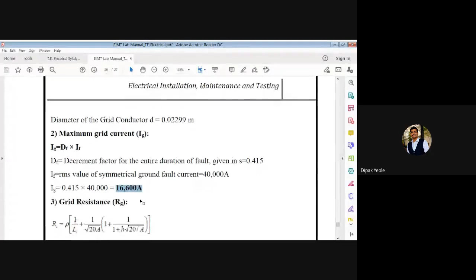After having the design grid current, we have to go for grid resistance. What is the grid resistance? Also there is one formula. You have to use that formula directly, put all the values together, and you will get the grid resistance. You can see over here the grid resistance is minimum, and if your value comes high, then there is something wrong in your data. So depending on the data, we have to find the grid resistance, and it should be less than 5 ohm. Our value is less than 1 ohm, so it is acceptable.